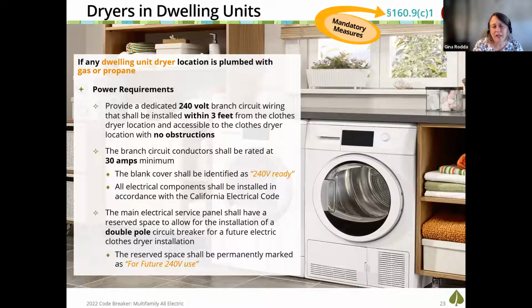So if I'm going to put in a gas dryer or a gas connection that can be used at the dryer location, let's say you're not installing the dryer, you're just putting that infrastructure in, you're going to, I'm sure this will be shocking, put in a dedicated 240 volt branch circuit wiring within 3 feet of that dryer location that has no obstructions and is accessible. You're going to do another 30 amp branch circuit conductor, and you're going to have another double pole circuit breaker in that main electrical panel serving the dwelling unit.